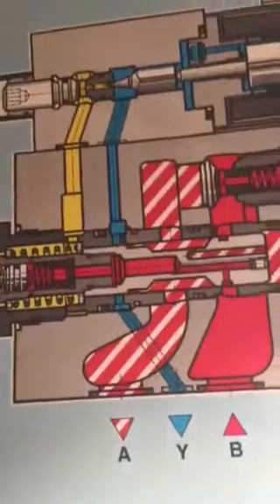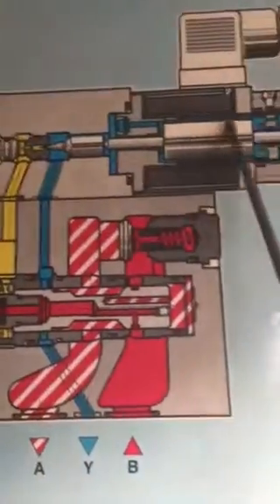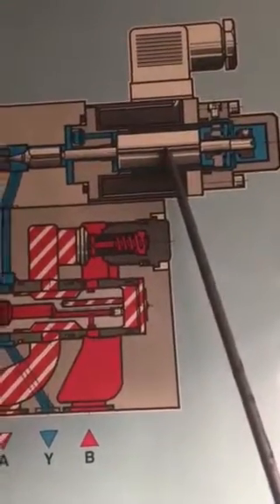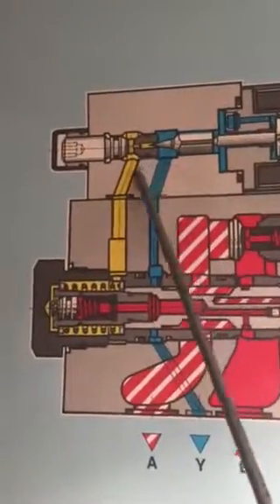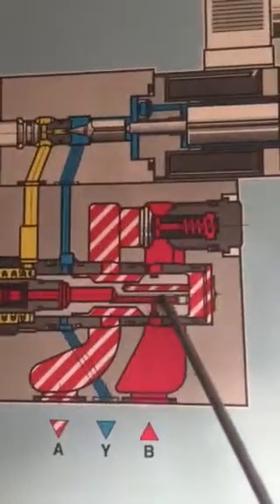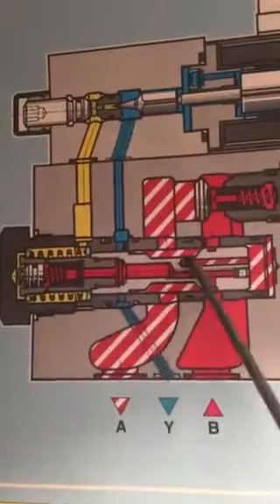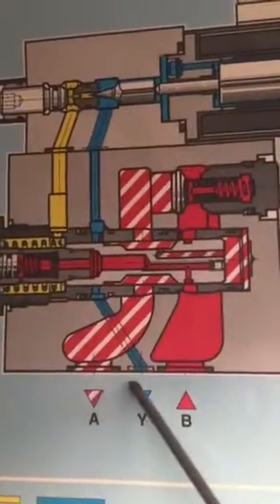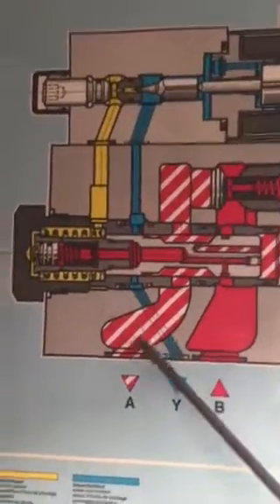This is the proportional pressure reducing valve, DRE, and it is controlled by the electronic card. This is the pictorial diagram of the proportional pressure reducing valve. This is the proportional coil — a magnetic force or force coil. An electric signal is called from here, and a proportional signal is given, which controls the position of this spool, and hence the pressure is controlled in a different section.